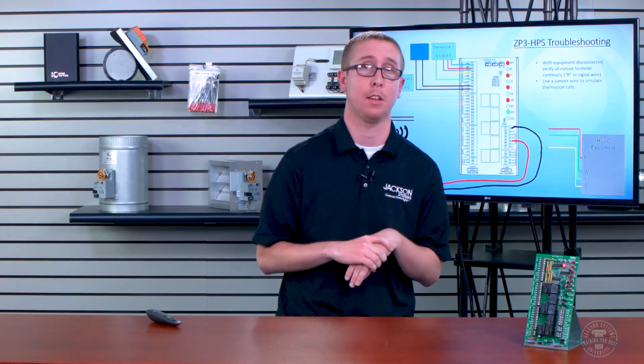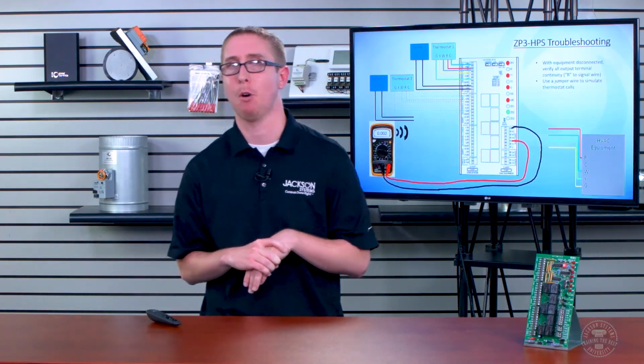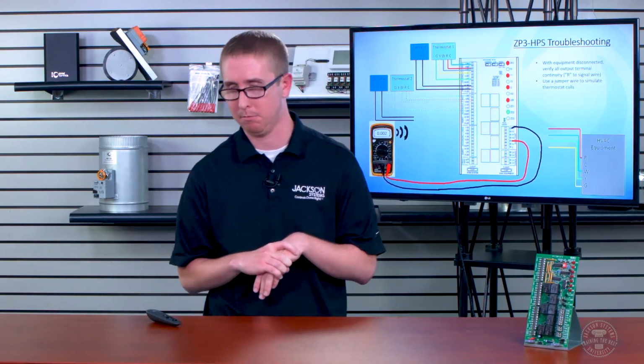So I believe the answer is yes, but the answer I can be 100% certain of is that if the damper itself has a shaft of a 1/2 inch width or 5/8 inch width, then the Belimo actuator will fit on it. If it is smaller than that, it probably will not. We have a bunch of different shaft adapters available.